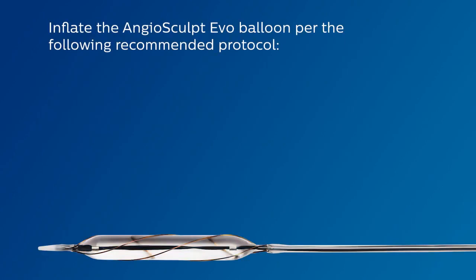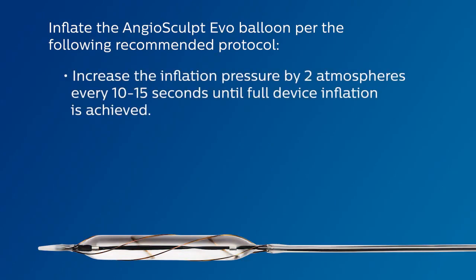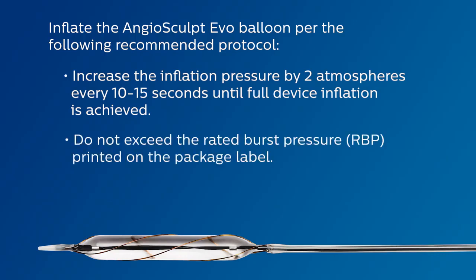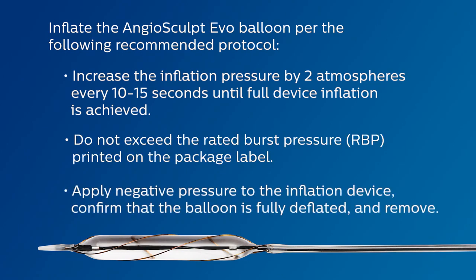Inflate the AngioSculpt Evo balloon per the following recommended protocol. Increase the inflation pressure by 2 atmospheres every 10 to 15 seconds until full device inflation is achieved. Do not exceed the rated burst pressure, RBP, printed on the package label. Apply negative pressure to the inflation device. Confirm that the balloon is fully deflated and remove.